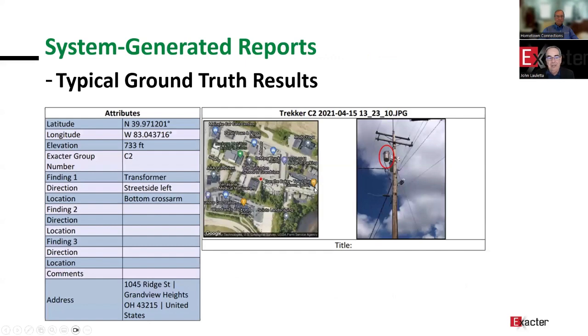And this is what the utility gets: a complete description of the location of the pole that has the problem, a satellite view of where that pole is. You might be in the area doing other work and want to pick this up as an adjunct job, and a high-res photograph of the piece of equipment that is in this incipient fault mode. It's going to fail. If you pull it out and replace it, it won't fail. If you leave it in, it's going to fail. And that's really the proposition that we offer.